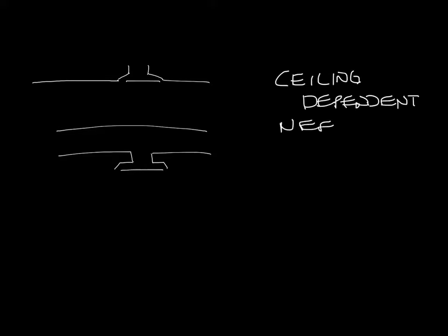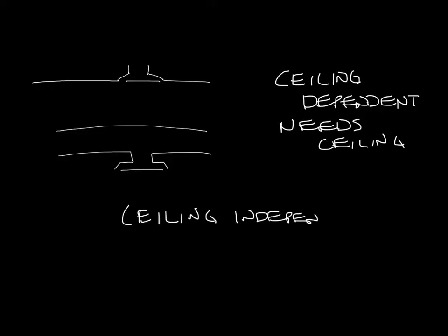Many people don't realize that the ceiling actually contributes to the performance of the diffuser. A while back I discussed ceiling dependent versus ceiling independent diffusers. This is where that becomes really important. Let me make a little room to write here. As a quick refresher, ceiling dependent diffusers need a ceiling to maintain their air pattern, and ceiling independent diffusers do not need a ceiling to maintain their air pattern.